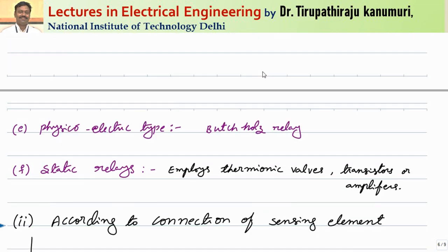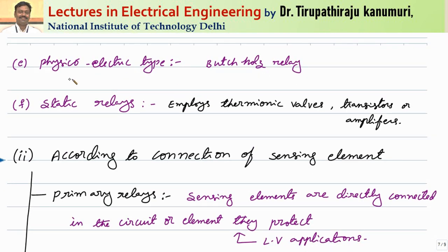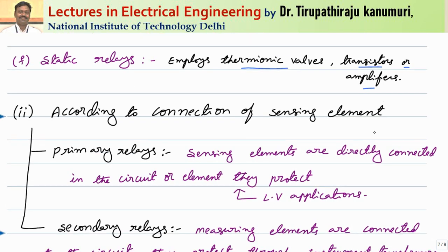The next type is the physico-electric type, with the Buchholz relay as an example. This relay is used with transformers to find incipient faults or slowly growing faults. Then there are static relays, which employ either thermionic valves, transistors, or amplifiers for their operation. As they involve only static elements, there are no moving parts — that is why they are called static relays. Their advantage is minimum power consumption.